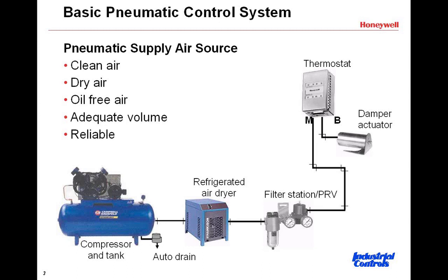In this particular case, we have a brand here that's Hankison, which is a pretty popular brand name. On Hankison units, you're going to have a power-on light that should be checked. There will also be a light on these Hankison — and perhaps other brands as well — that indicates high temperature warnings, saying that there's a problem inside. This is basically like a window air conditioner that cools down the air, dragging and pulling moisture out of the air and bringing it to the drain.